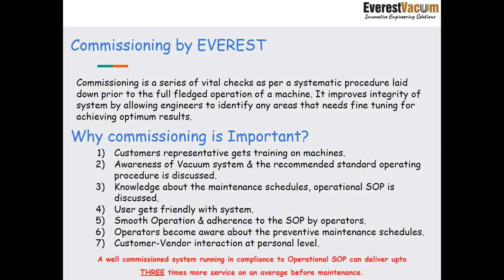So this is proven. We have commissioned many systems, and what has come out is that a well-commissioned system, if it is run in accordance with the operational SOP, can deliver up to 3 times more service on an average before maintenance. So that much criticality is there in commissioning. So we should get our systems commissioned, and standard operating procedures should be adhered to.